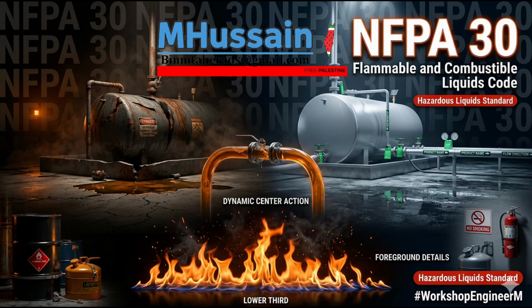Okay, so that covers the Class I family flashing below 100 degrees. What about the rest? The legacy combustible liquids, which are now Classes 2 and 3. So these are your liquids with the flash point at or above 100 degrees Fahrenheit. Class 2 is from 100 up to, but not including, 140 degrees.